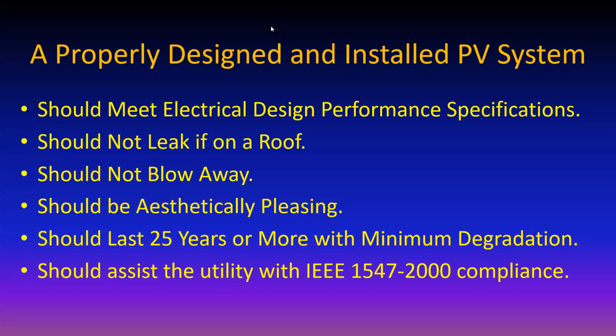And usually you don't want to put modules in those locations anyway, because the wind loads tend to be higher at the edges of the roof. So there's another provision, and we're going to come to that, called rapid shutdown, where one flip of one switch shuts down the entire system. Right now, the rules are that if you have electricity coming out of the photovoltaic array, it can't go any further than the boundaries of the array, and there is no photovoltaic electricity anywhere else. So yeah, a lot of thought has gone into making sure the firefighters are happy. I can remember designing a megawatt system for Orlando almost 15 years ago, where one of the main people who sat down at the table was the fire marshal, who we wanted to make sure we made happy. So in general, folks are paying attention to fire requirements.